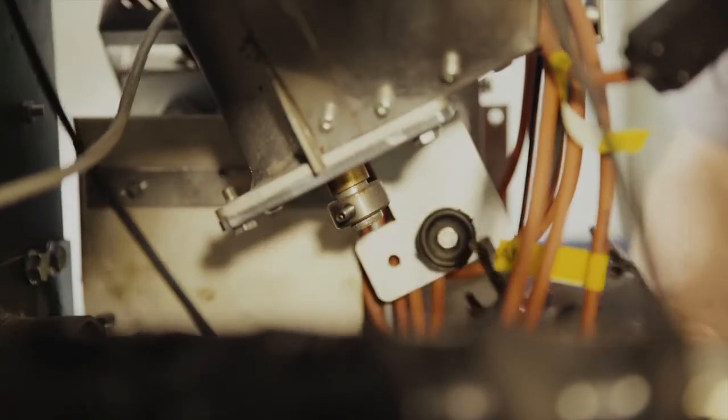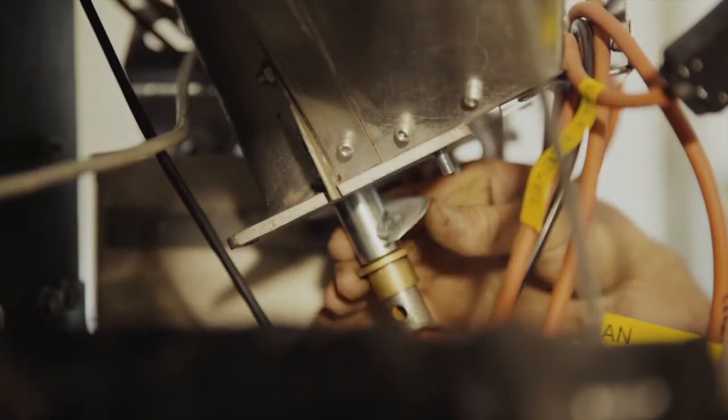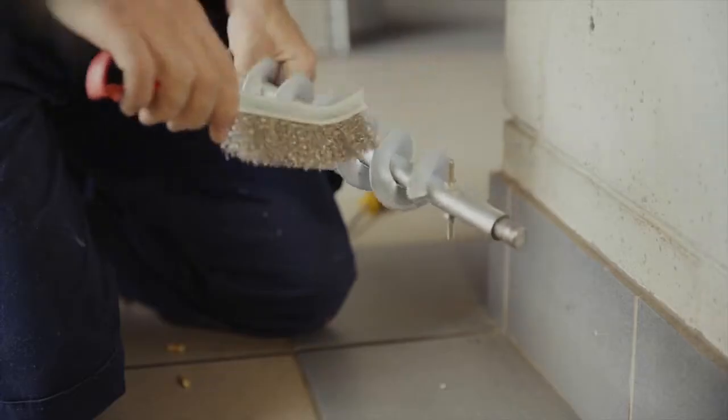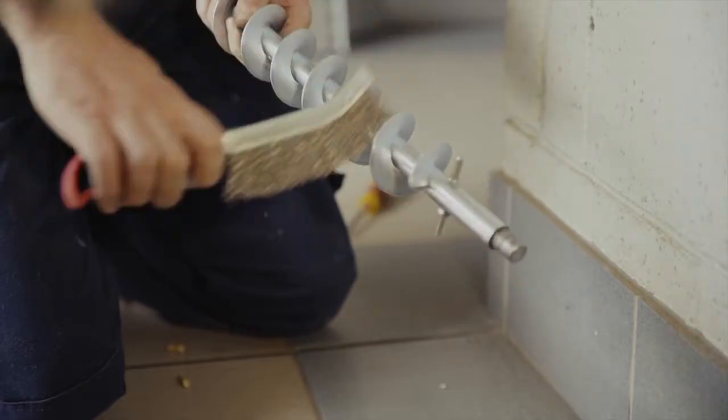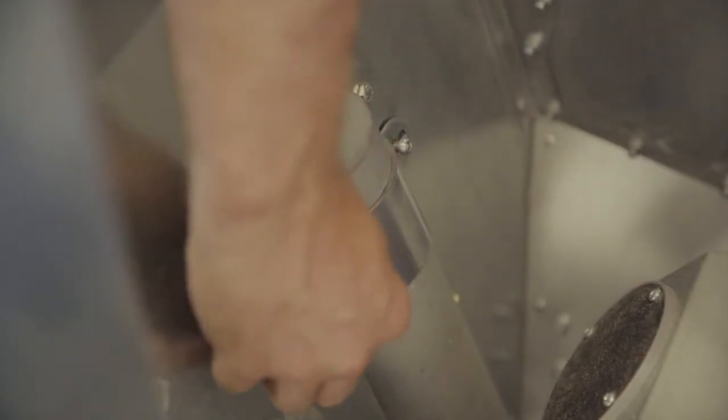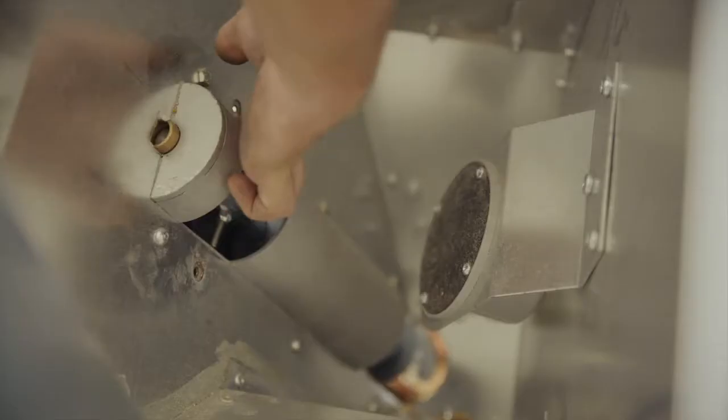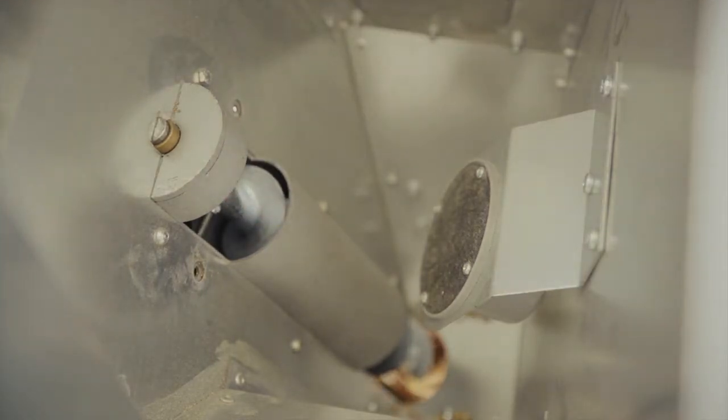Disconnect and remove the auger motor. Firstly, remove the motor off the auger shaft, then unfix the motor bracket from the auger. Then withdraw the auger shaft from the hopper as shown here. Remove the auger and clean out any dust or debris. Check the auger bushing. To put the auger back in, remove the inspection cover of the auger housing in the hopper. Guide the auger shaft back into the top bushing and fix the motor bracket back in place.